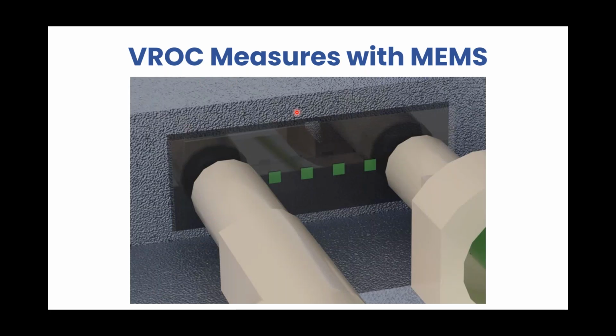I'll explain it instead. And we push the sample at a well-controlled shear rate through this microfluidic channel here. So it's about 20 to 50 microns thick. So the sample is going this way through the channel and then out this outlet. So as the fluid is flowing, you have the pressure sensors detecting a linear pressure drop along the channel during the flow.